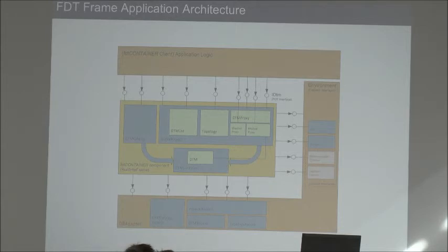Network information like bus address, instance data, process data, all these are the information you get via the DTM proxy, depending on the device type, which is represented by the DTM. So features like going online, going offline, upload, download of parameters, things like this. Hardware scan.